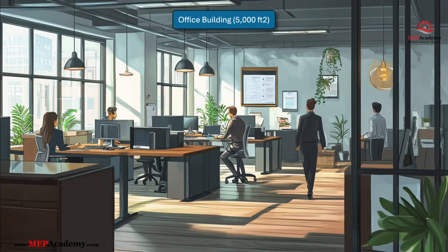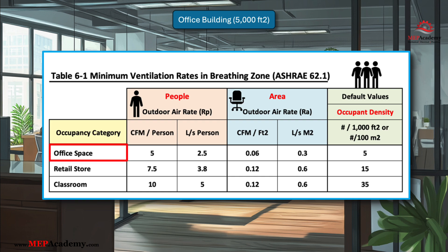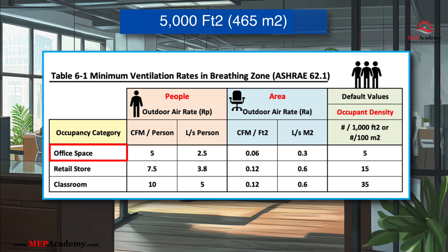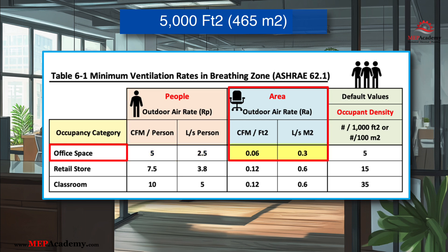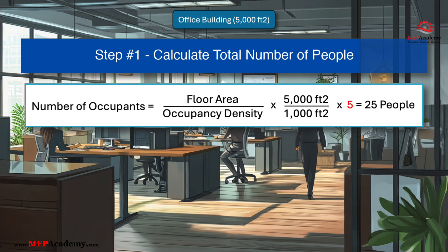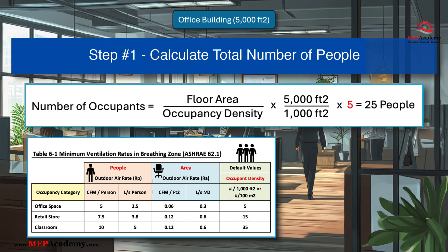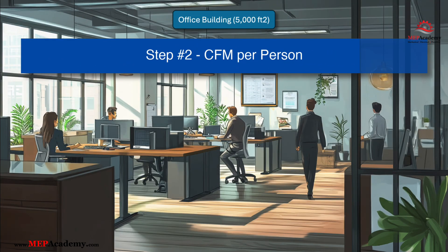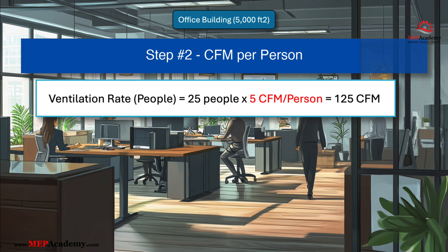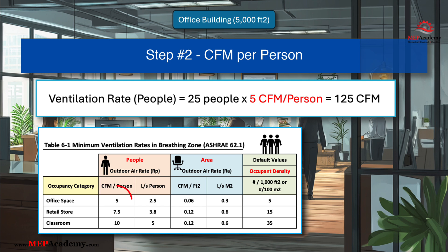Example 1: Office Space. Given data — Occupancy Type: Office Space; Floor Area: 5,000 sq ft; Occupancy Density: 5 people per 1,000 sq ft (per ASHRAE 62.1 Table); Outdoor air rate per person: 5 CFM per person; Outdoor air rate per area: 0.06 CFM per sq ft. Step 1: Calculate the total number of occupants. Number of occupants = (5,000 sq ft / 1,000 sq ft) × 5 people per 1,000 sq ft = 25 people. Step 2: Calculate the ventilation rate required for occupants. Ventilation rate (people) = number of occupants × outdoor air rate per person = 25 people × 5 CFM per person = 125 CFM.